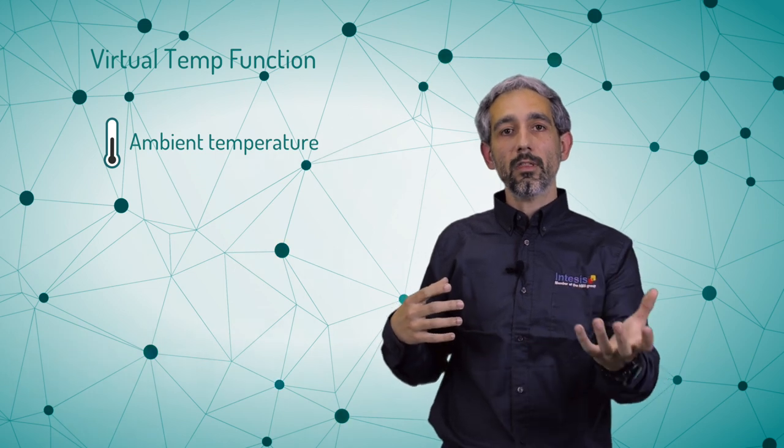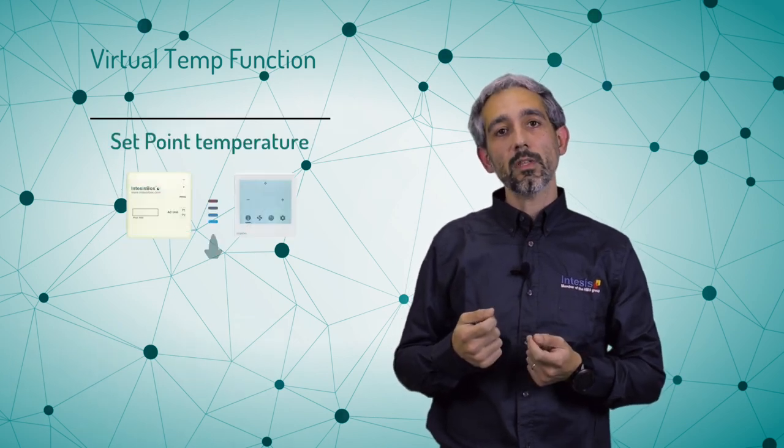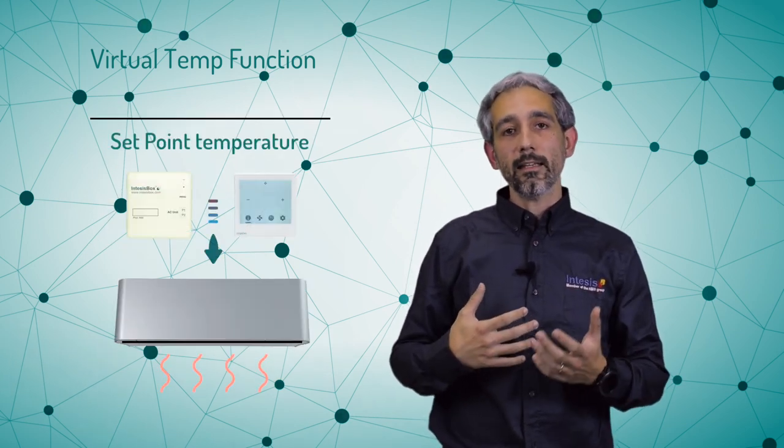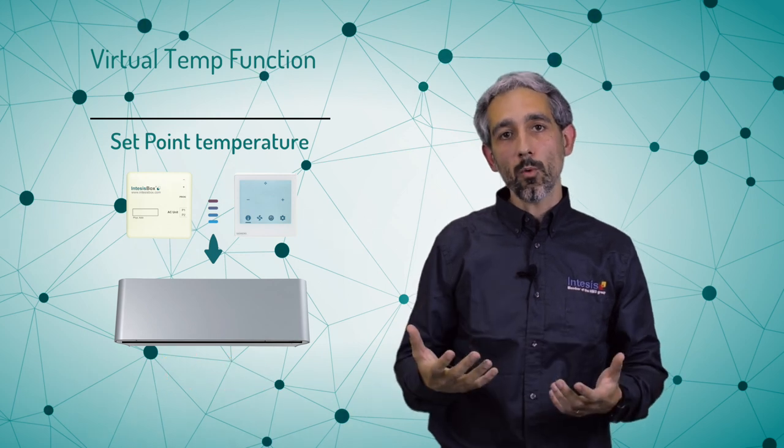In that case, what we do is collect in the same way this external source of information of the ambient temperature and compare it with the information that we have from the AC system. Then, calculating this difference, we adjust the setpoint so the AC unit is working and getting the temperatures that the user really wants in the room.